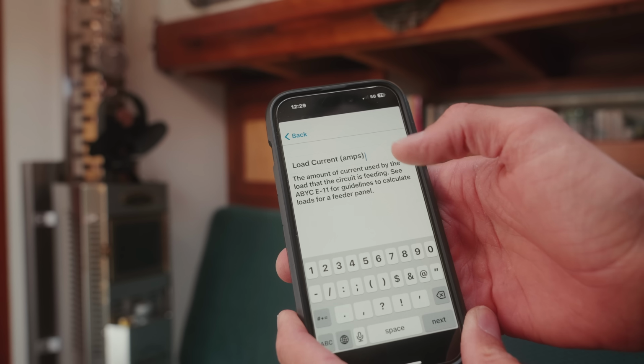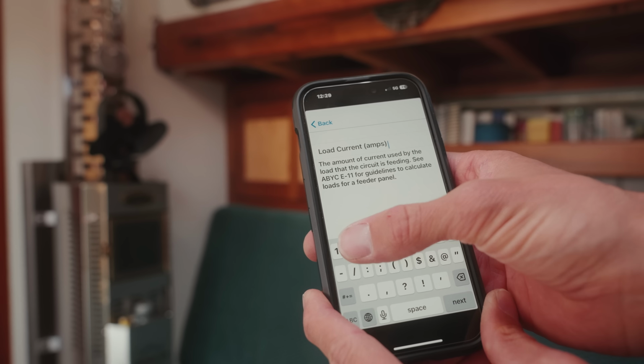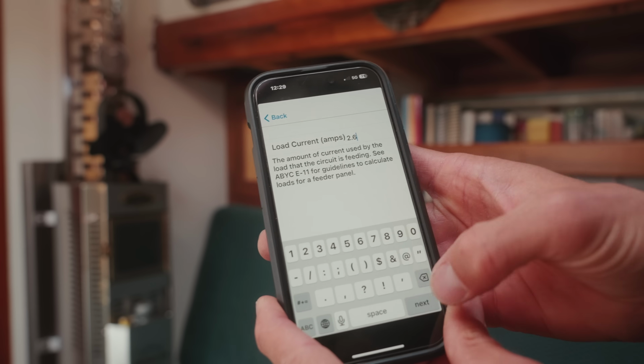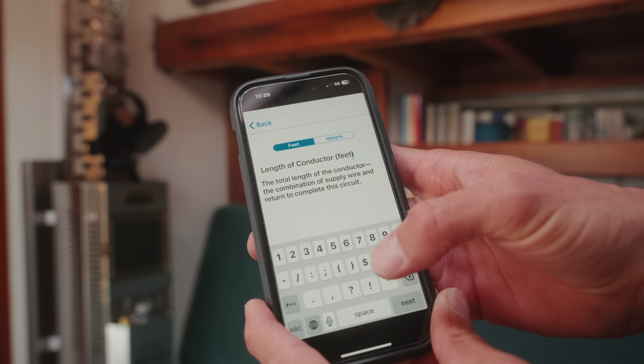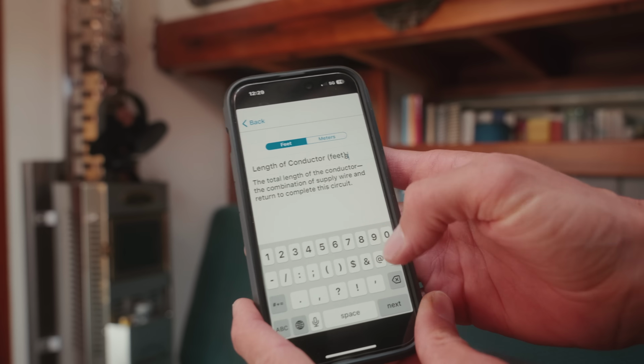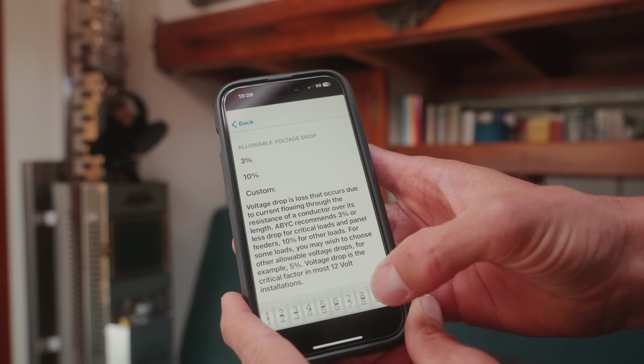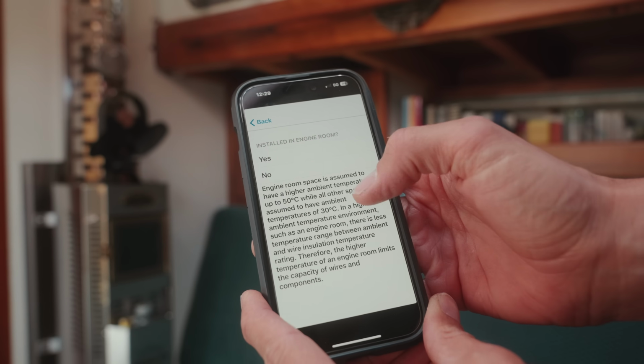When I open it, the first thing you put in is voltage, then the load you're planning to power, so how many amps that would draw, the length of the conductor, and the allowed voltage drop, anywhere from 3 to 5% on a boat. Then the insulation temperature rating, which for all the cables I bought is 105 degrees.